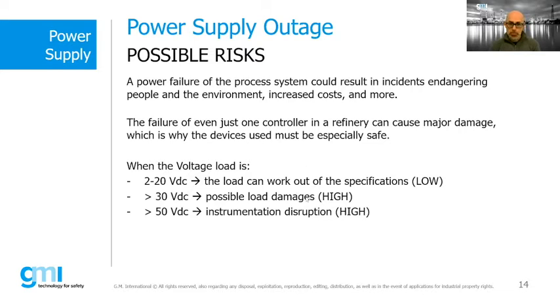The second dangerous failure condition of a power supply is when the output voltage reaches a value higher than 30 volts. In this condition, the load is subjected to an extra voltage which can damage it, or in case of output voltage higher than 50 volts, the field instrument can suffer a definite disruption. We can take, for example, an engine cooling system which works thanks to a standard power supply. Suppose that the standard power supply fails and goes into an overvoltage condition, damaging the cooling system. This will lead to an overheating of the engine, which will lead to serious consequences for the whole system connected to it. Once again, I want to underline the value of having a safety power supply system which guarantees us high performance and high safety.